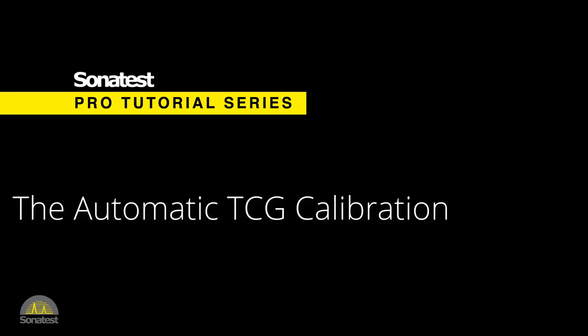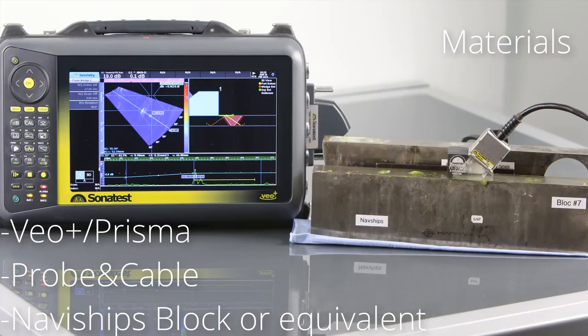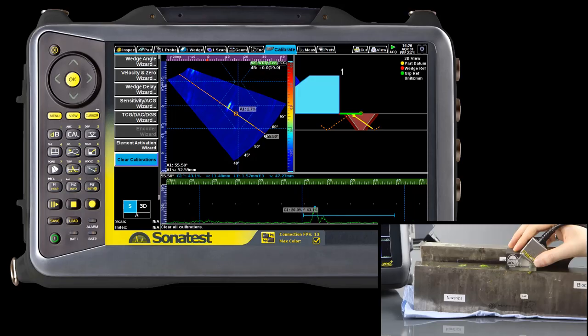The purpose of this calibration is to equalise the amplitude of the response from a reflector for all of the angles at different depths. This calibration is meant to counter the attenuation of the signal response of the sound propagation inside the material. For this calibration, you're going to need a Veo Plus or Prisma, a probe and cable, and a Navships block or equivalent TCG block.